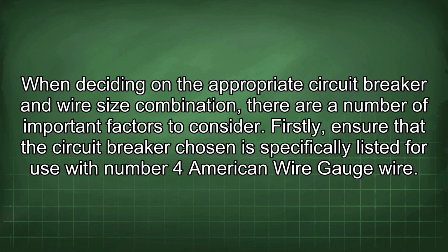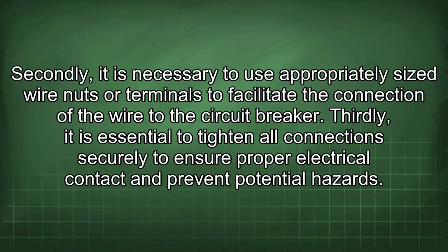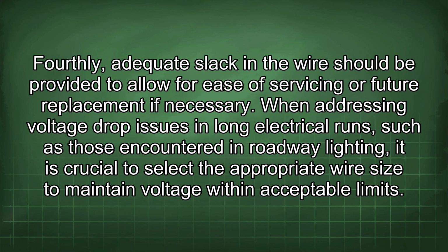When deciding on the appropriate circuit breaker and wire size combination, there are a number of important factors to consider. Firstly, ensure that the circuit breaker chosen is specifically listed for use with number 4 American wire gauge wire. Secondly, it is necessary to use appropriately sized wire nuts or terminals to facilitate the connection of the wire to the circuit breaker. Thirdly, it is essential to tighten all connections securely to ensure proper electrical contact and prevent potential hazards. Fourthly, adequate slack in the wire should be provided to allow for ease of servicing or future replacement if necessary.